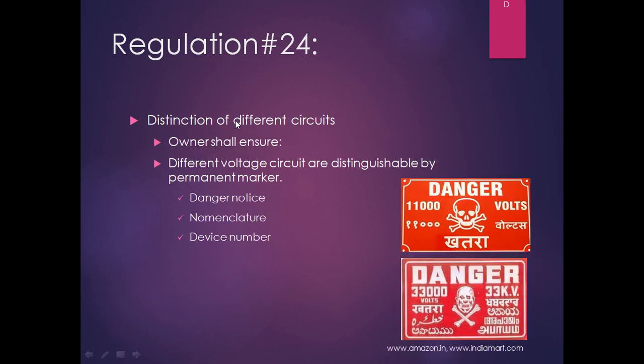Regulation 24 is regarding distinction of different circuits. The owner shall ensure different voltage circuits are distinguishable by permanent marker. Now the permanent marker may be a danger notice, like you have some equipment for 11 kV, you affix an 11 kV danger notice in front of that, and you have some equipment of 33 kV, you affix a danger notice stating 33 kV in front of that. Somebody also uses different nomenclature. You may use AA for 11 kV, BB for 33 kV, something like that, and somebody may use different device numbers. Suppose one relay is used for 11 kV, you mention it 186. If it is used for 33 kV, you mention it 286 or 386. These things are very common practice in the industry.